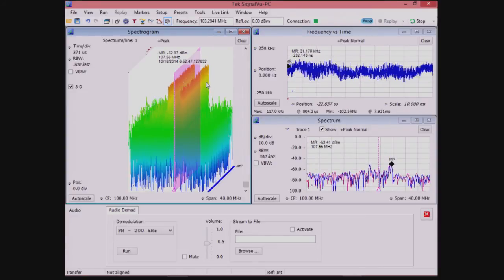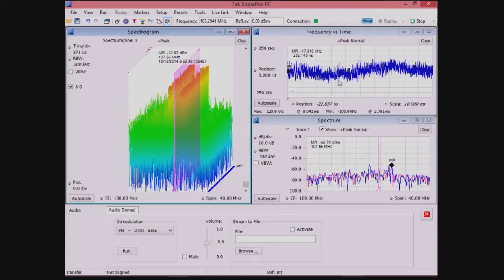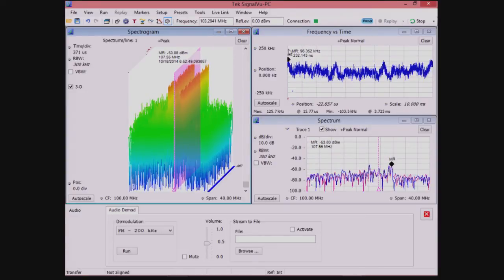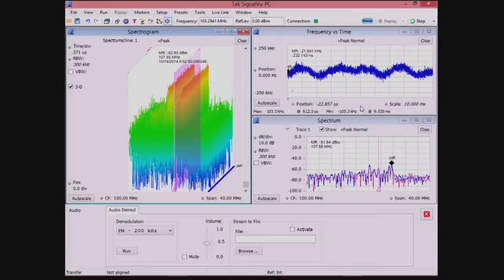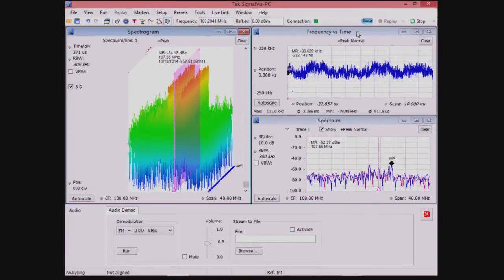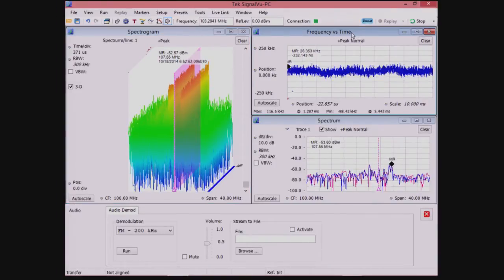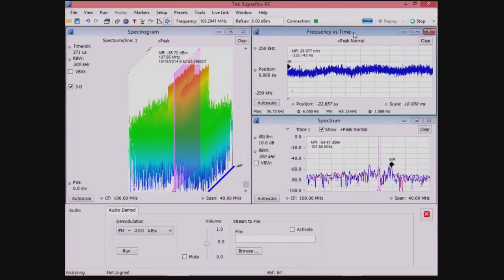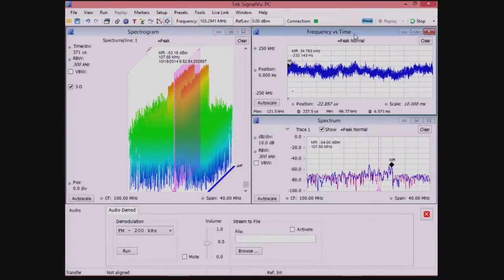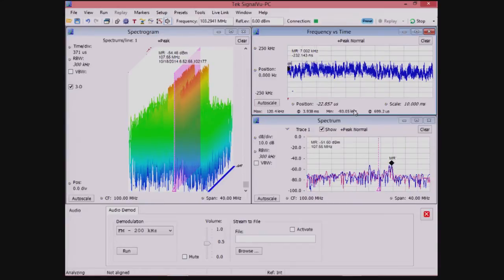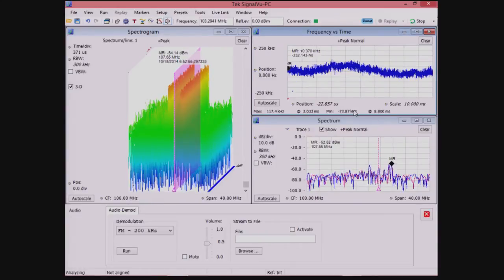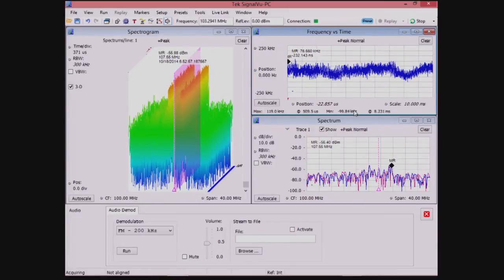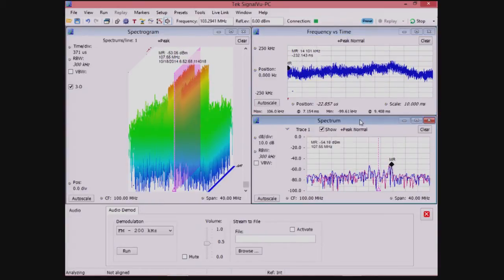In the upper right corner, we see the FM versus time display, as well as readouts of the FM measurements. In the lower right corner, we see the spectrum display. This corresponds to one time slice of the spectrogram display.